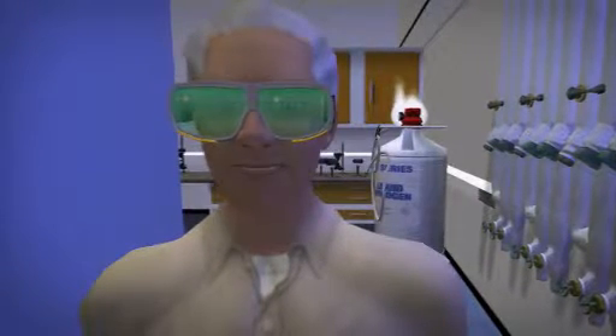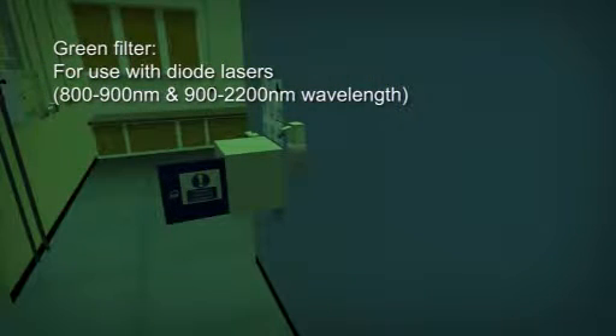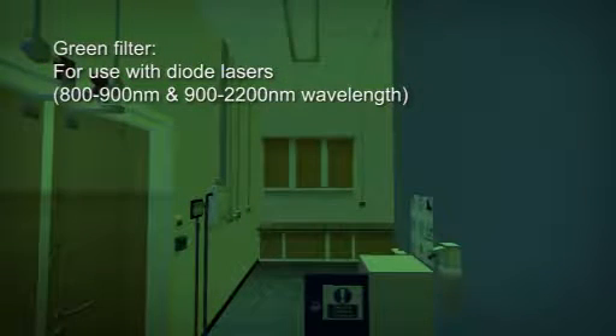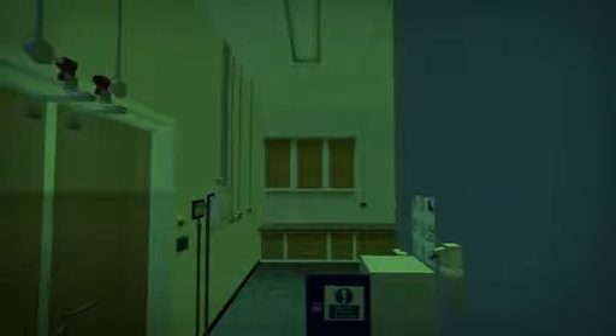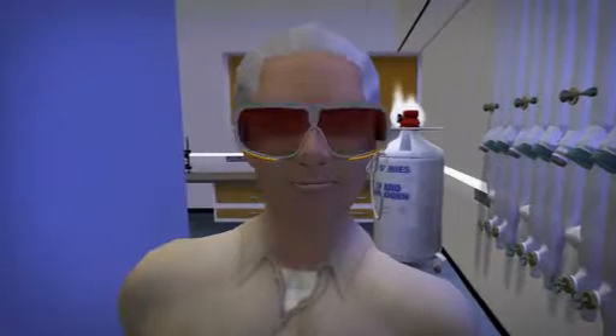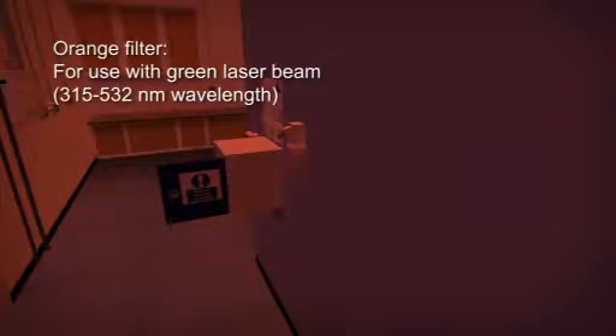Laser goggles can provide protection from single or multiple laser sources, but generally, the more laser wavelengths that the goggles protect against, the less usable they are. This is because less light is transmitted through the filter and certain colors are obscured, making it difficult to see clearly. With this in mind, there may be a tendency to want to remove the goggles to see more clearly.